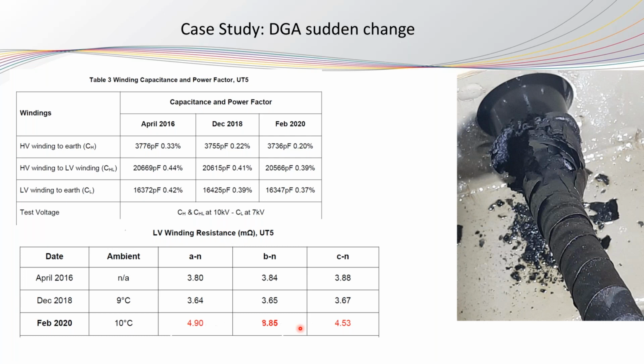And when Doble did this investigation, we found that the middle phase insulation was damaged, and this was the cause of the unexplained DC winding resistance, and of course the sudden change in the dissolved gas analysis that was detected by the online monitoring.